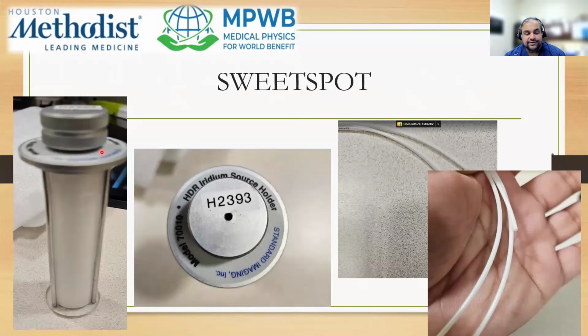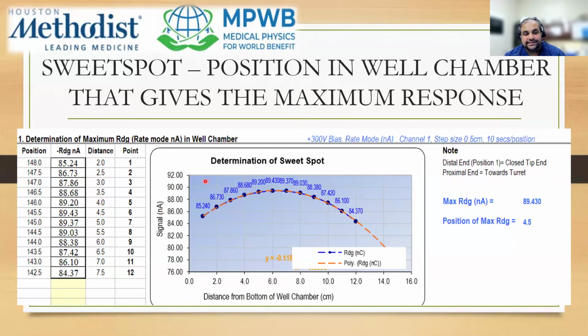This is what your source holder looks like that goes inside the well chamber. You insert the end that is closed, while this end is where you can add the connector that goes into the turret of your afterloader. The first test you always do is the sweet spot. The sweet spot is the position in your well chamber that gives you the highest reading, and all your subsequent tests will be done at the sweet spot location.